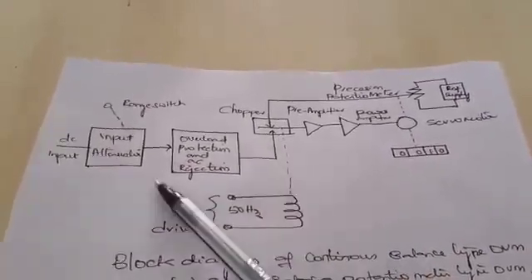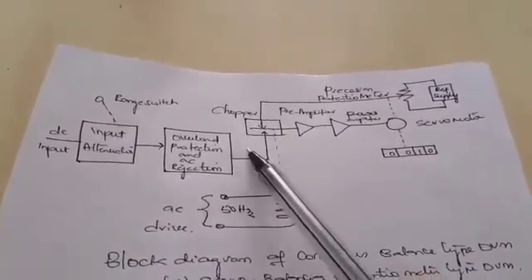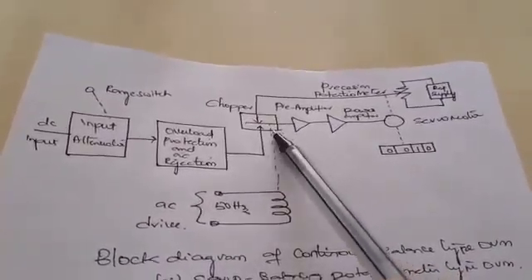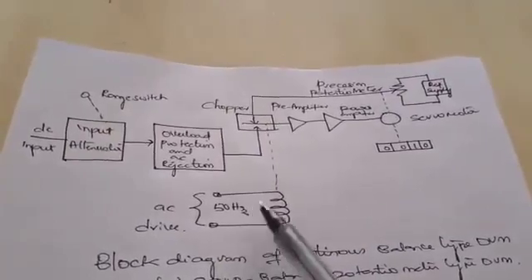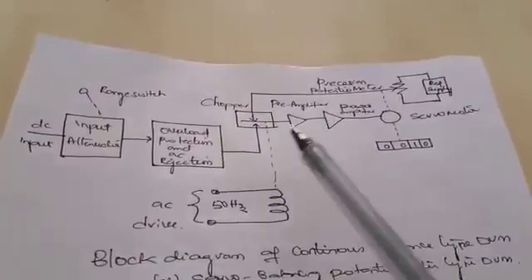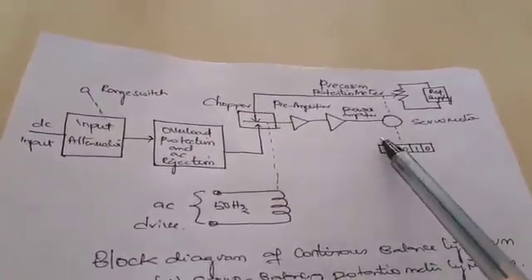The DC supplies of both the input voltage and the reference voltage are compared, and the difference in voltages produces some output — generally a square wave signal. That square wave signal is driven using an AC drive circuit at a line frequency of 50 Hz, then given to the preamplifier and power amplifier where the signal is amplified, generating pulses required to operate the servo motor.